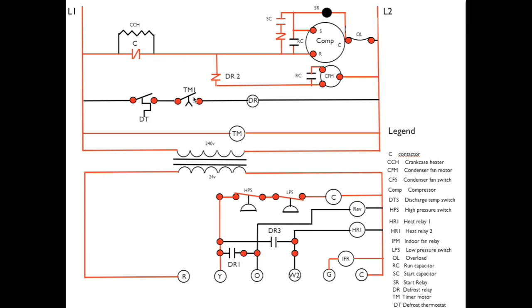If this opens in 10 minutes, it goes out of defrost. If it doesn't, the TM1 switch will open and take it out of defrost, then go another hour to check for defrost again.